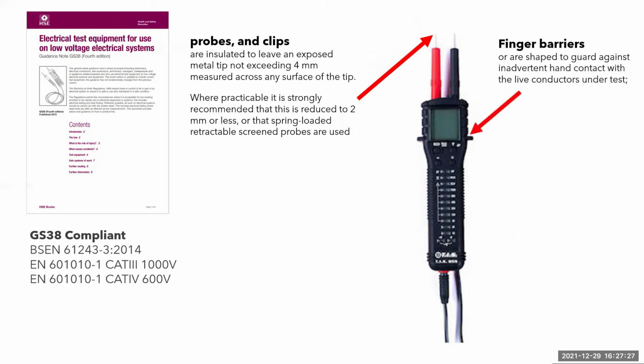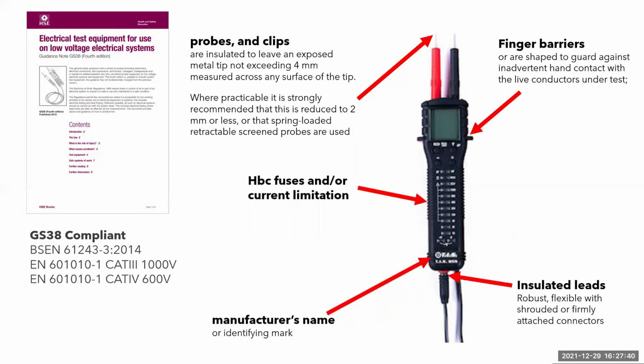It needs to have finger barriers to stop you from slipping into the live terminals as you're pushing the test probes into them. Insulated and durable leads that won't get damaged easily, the manufacturer's name, and possibly even a high breaking capacity fuse and/or current limitation. For those of you that don't know, current limitation is where the internal resistance is so high that current cannot flow easily. This protects you from having a highly dangerous probe tip waving around when the other probe is connected to the line terminal.